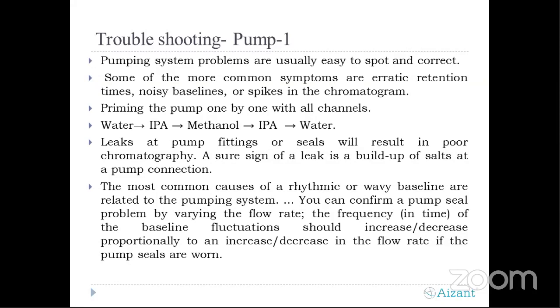If you are finding the root cause, it's easy to identify problems related to the pump, which you can easily find through erratic retention time. Once you start your system, you'll find the retention time is 5 minutes, then 6 minutes, then 7 minutes, or erratic. Sometimes it's 7, then 3, then 4. You also find multiple spikes or a noisy baseline, because it will give a pressure dumping which will be observed in the detector.